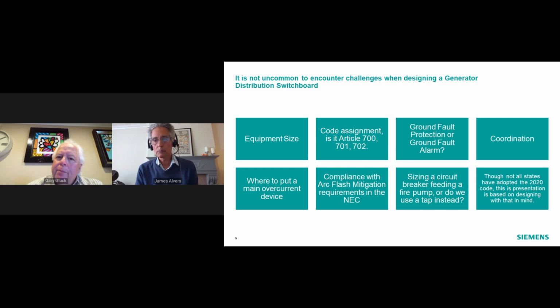When it comes to fire pump, how do we do that? There seems to be confusion between what's required in the normal part of the system versus the emergency part of the system. And so we'll talk about how that works with generator distribution switchboards. And then the final consideration will be that this presentation is going to be based on NEC 2020. Before you get excited that your state's not on 2020, don't worry. While there's been a lot of changes in 2020, the changes that would be applicable for what we're going to talk about aren't really affected by the content.